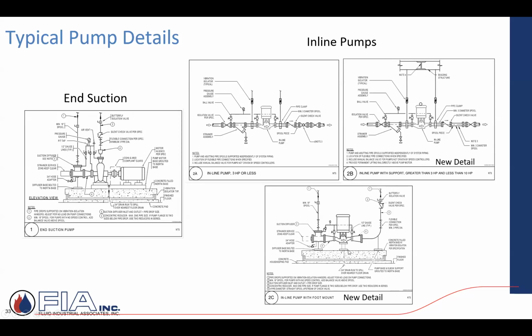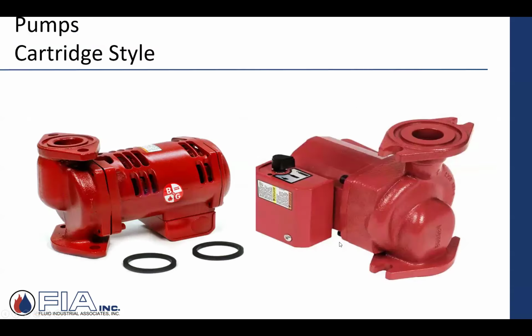And then as you get over that 10 horse, that's when you're going to get into that split coupled vertical inline. They'll actually have a spool piece and a base to support, because you're dealing with some serious, substantial weight. And then foot supports on the piping on the discharge side, as well as, in this case, they're actually using that suction diffuser on the suction side of that large capacity inline. So there's options.